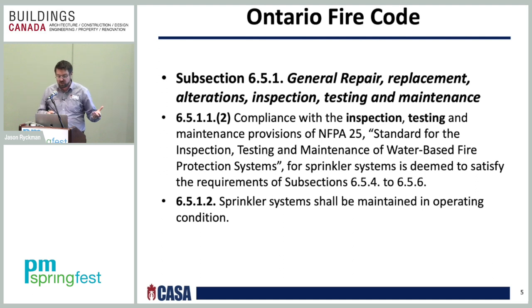So the rest of those sections that are used in the fire code still have to be used. So I'll just repeat myself again. NFPA 25 can only be used for section 654 to 656. And in everything else, you still have to use the fire code. So 6512, sprinkler systems shall be maintained in operating condition. Okay?